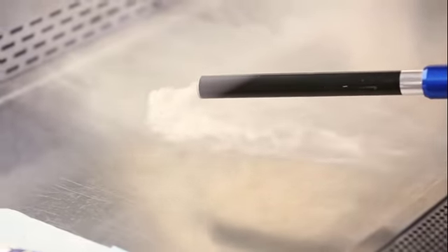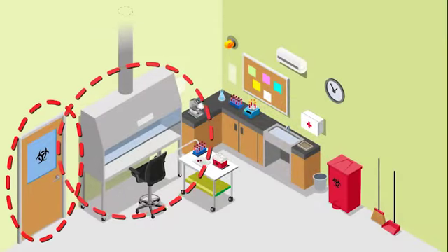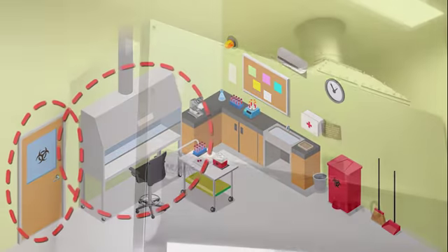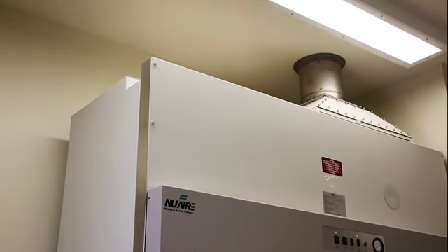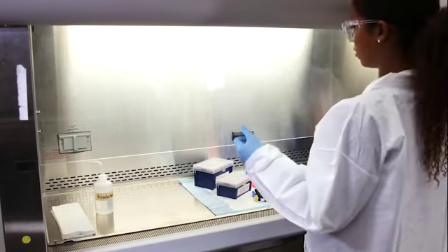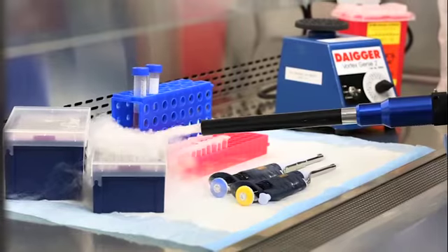The physical location of the BSC can affect the airflow as well. Placing a BSC too close to a doorway can cause the air to be drawn out of the BSC when a door is open. Placing a BSC too close to an HVAC supply vent can also interfere with the BSC containment. Proper sash height is critical because when the sash is kept at the proper height, the appropriate inward airflow